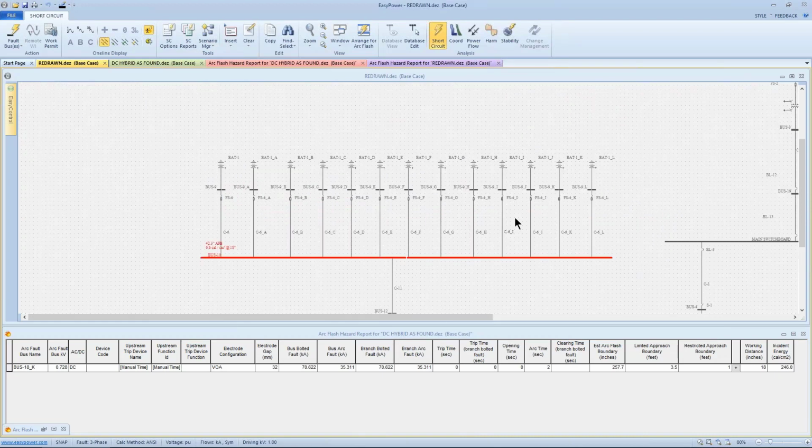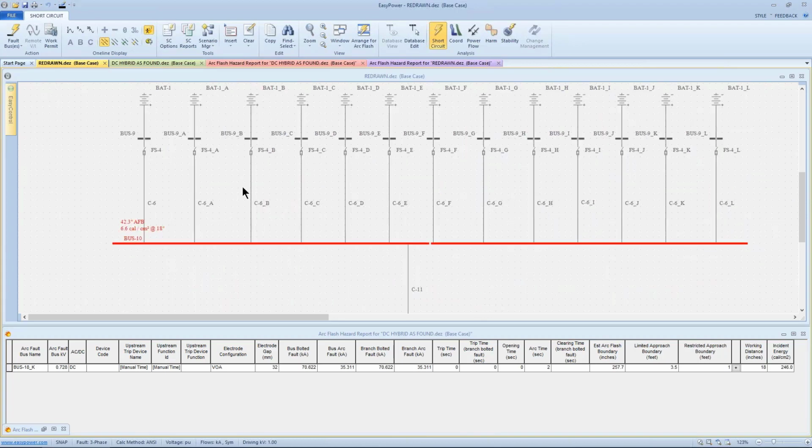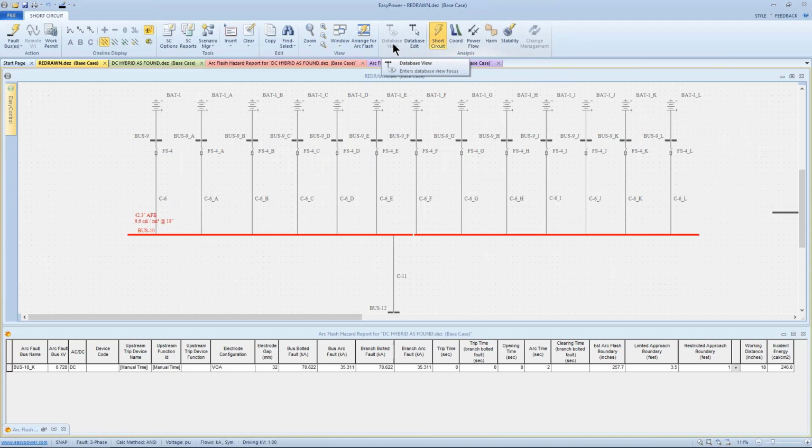Quite literally, the only difference between this system and the one we looked at a few minutes earlier is the location in the model of where this fuse is placed. So it doesn't matter as far as the simulation and power flow. It does matter on the way the calculations are made for bus protection. All right, so that's a word to the wise.